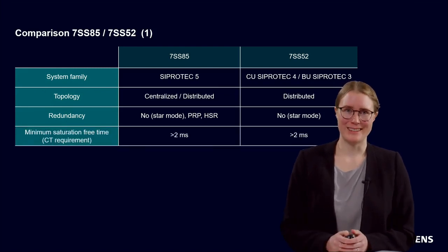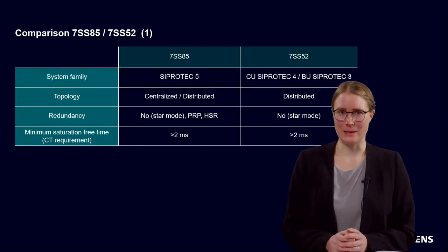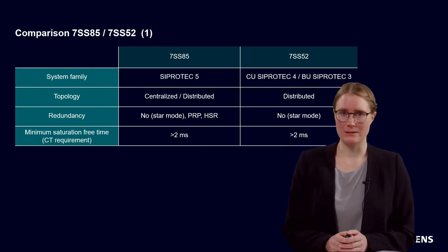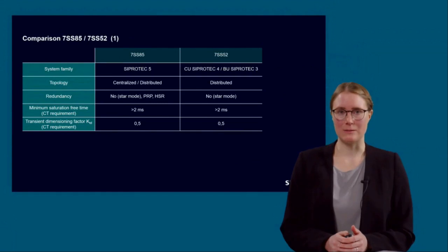Here we go. The requirements for the current transformers are the same for both devices. So for the minimum saturation-free time, we need a value greater than 2 milliseconds, and a transient dimensioning factor KTD of 0.5 in both cases. We will talk about CT dimensioning in the third tutorial. About additional functionality in the 7SS85, we have the really great benefit that you can integrate all the SIPROTEC 5 platform functionalities to the SIPROTEC 5 device that you want to use as a merging unit.